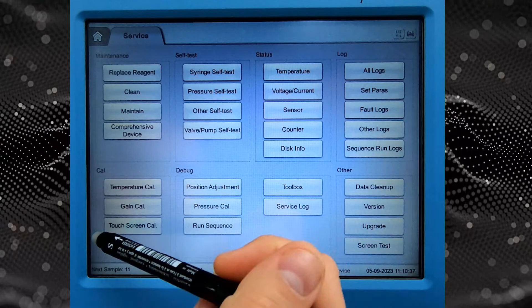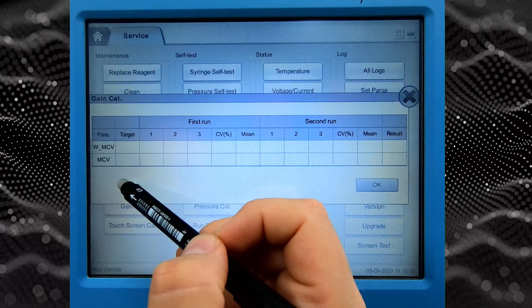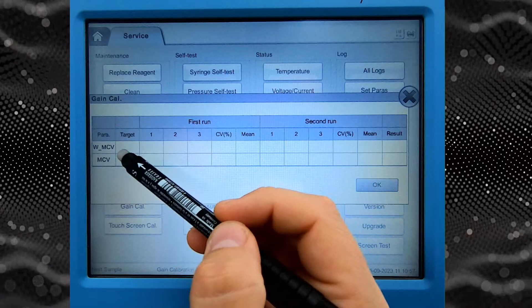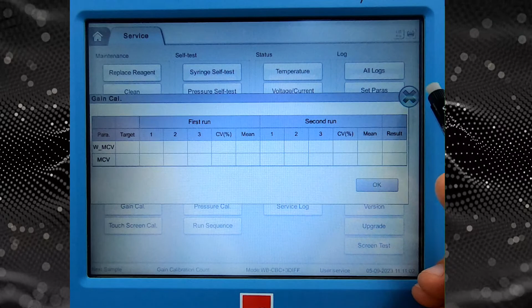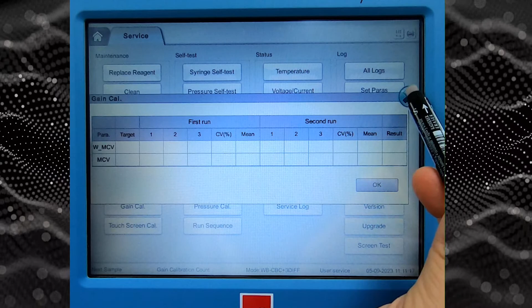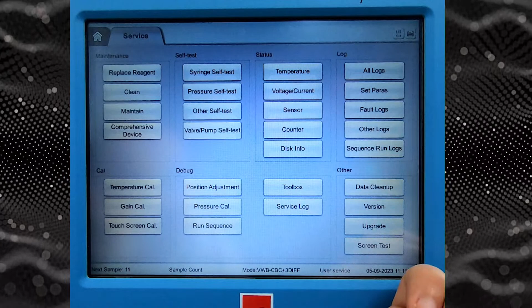Gain calibration. This is an additional menu, and this menu allows you to set the gains for the WBC channel and RBC channel according to some WMCV and MCV parameters or targets, as you can see. So you need to make these measurements, but this will be only useful when, for example, you replace the counting chambers, because on the new counting chambers, there is a possibility that the impedance channel is not identical. I mean, maybe the opening in the aperture is slightly different, or maybe part of the electrical circuit in the impedance channel is not identical.